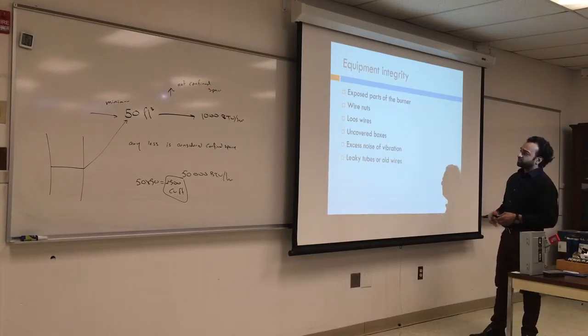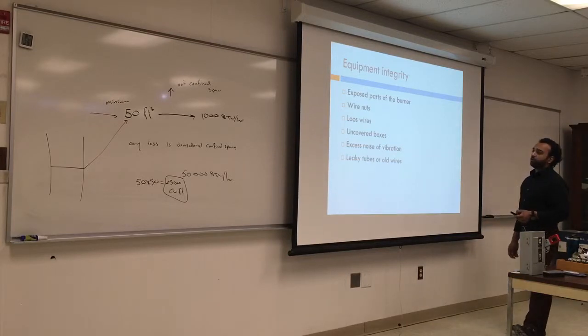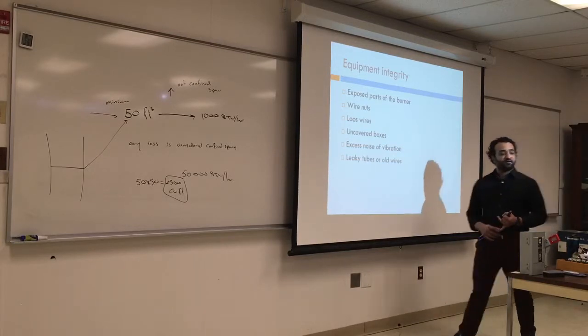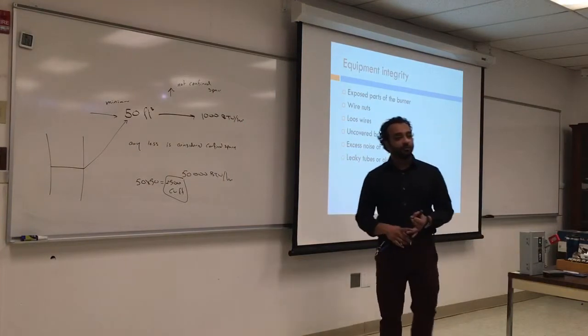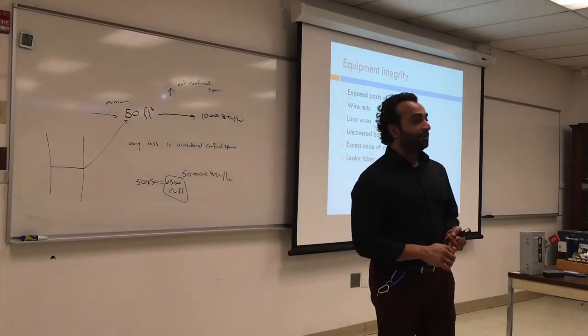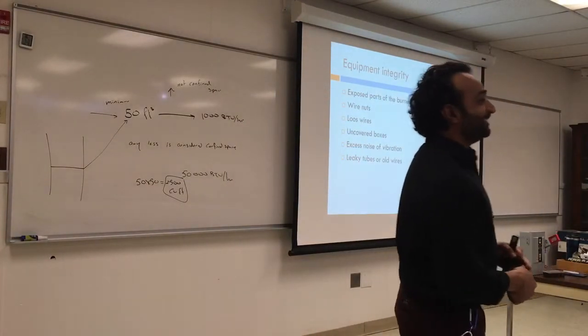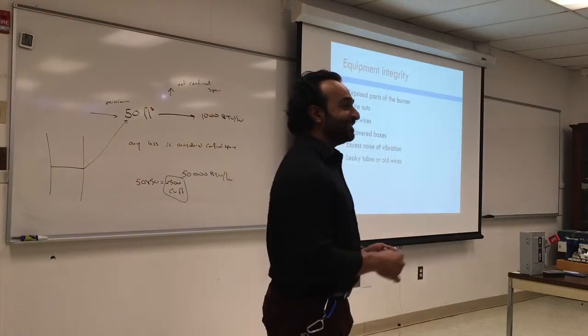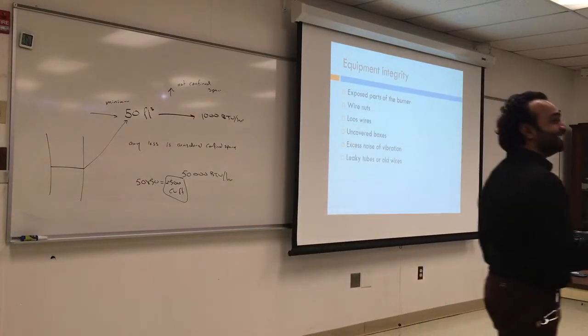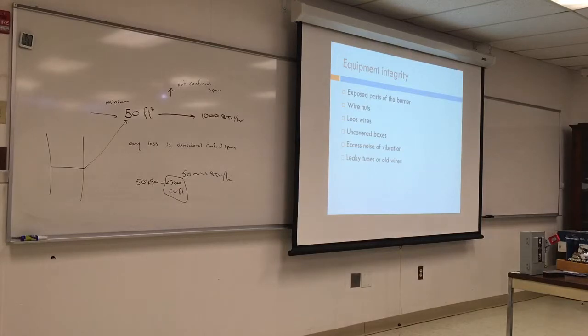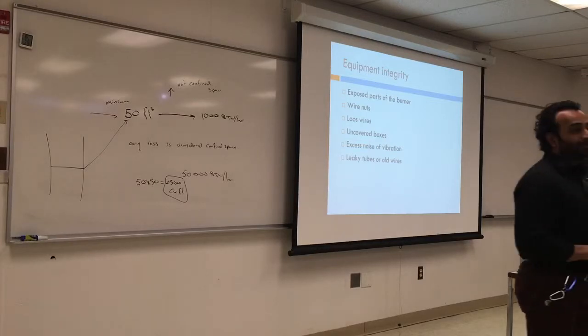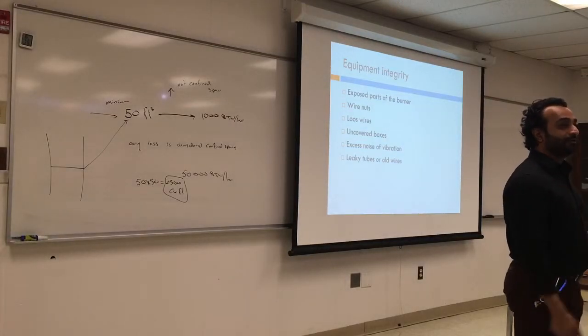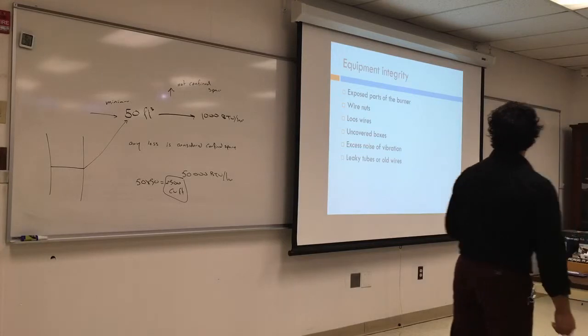Look for uncovered boxes. Check for excess noise or vibration that could come from the fan. Noise in the inducer fan can come from the motor. Something might have fallen in the inducer fan that has not been retrieved. A small piece falling in the inducer fan happens a lot, and over time it will rattle. Make sure to know where that rattling is from. Most of the time it wouldn't cause a problem, but you never know when this thing will fly off and get clogged and ruin your motor.